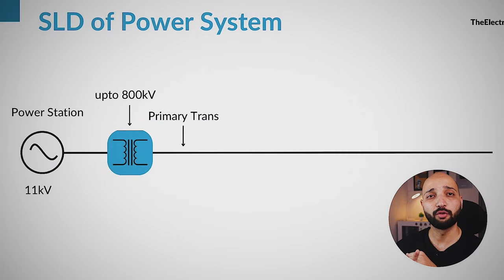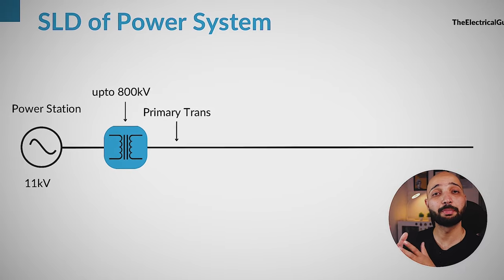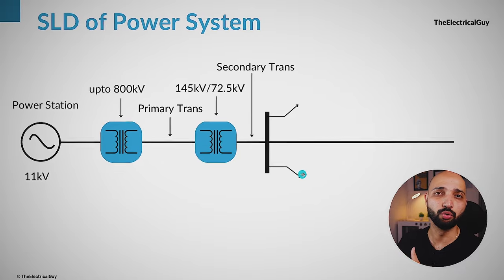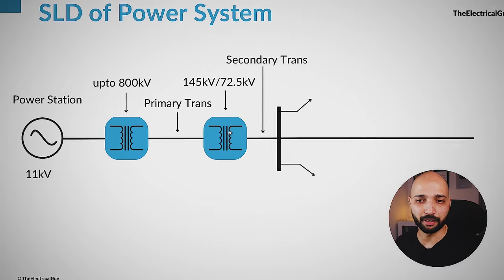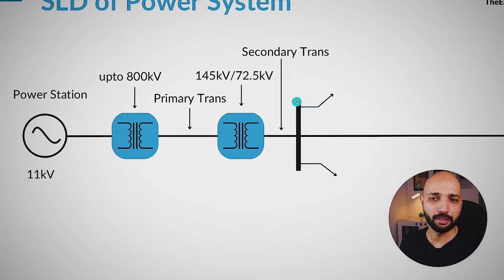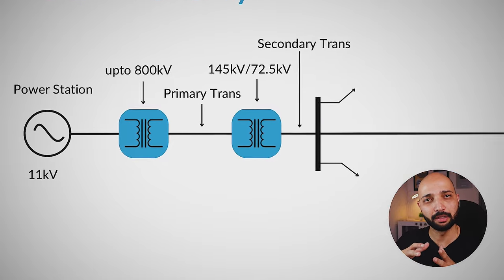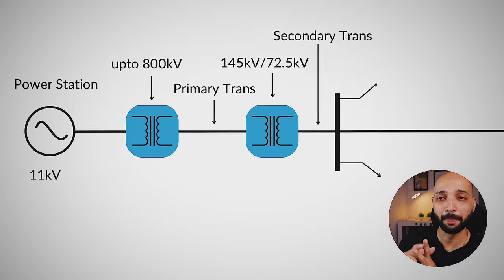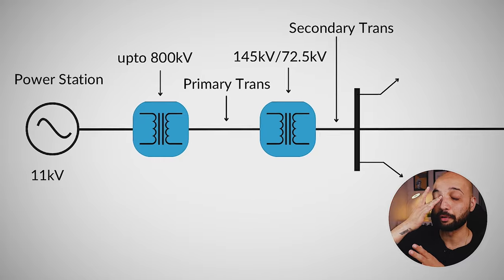Once the power reaches the receiving substation, it is stepped down to lower voltages — maybe 72.5kV. From here, power can also be supplied to some high-tension consumers who need 145kV or 72.5kV directly in their factory. Those consumers build their own step-down substation and take power from there.